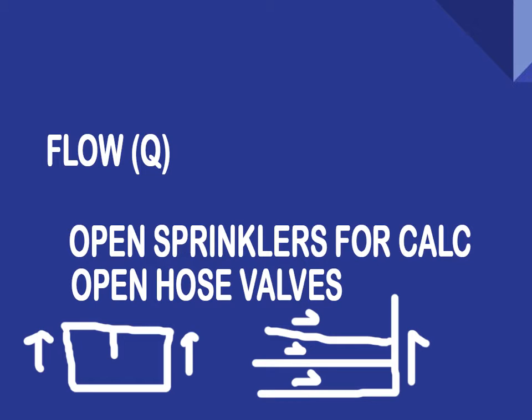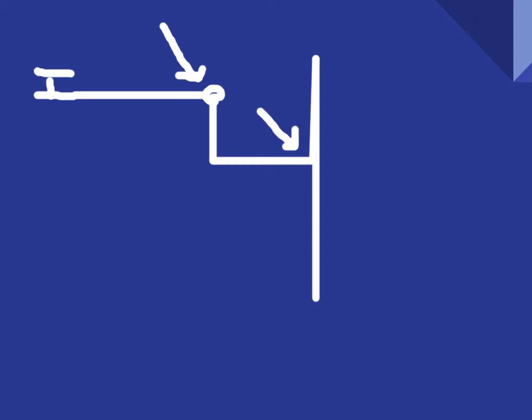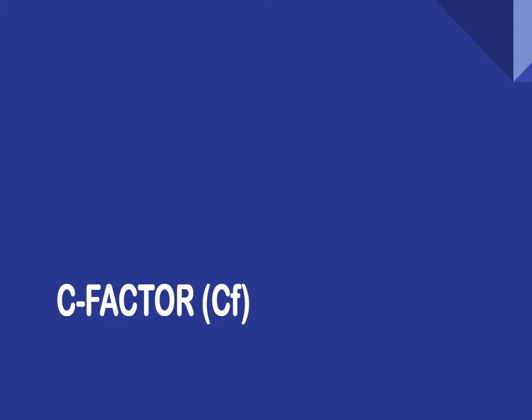The second factor we listed was internal pipe diameter. Since a change in this number changes the way the equation plays out, points of change should have their own node designation. Commonly, these are remote area branch line connections to cross main, connections to a standpipe, and base of riser connections. There will be other locations as we manipulate our pipe sizes to achieve safety factors, but these are the most common. The third thing we listed was C-factor, which behaves much like inside diameter, but tends to change much less often, typically only between a system header and the dry pipe it serves, and a system's connection point to the incoming underground.